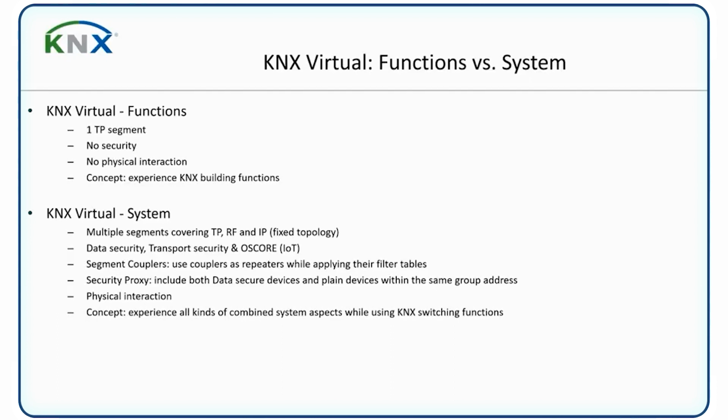So what is KNX Virtual System, to be more precise? In this virtual KNX installation, we will see multiple segments for different media types. So we will see twisted pair devices, radio frequency, IP devices, all that in a fixed topology, by the way. What we also have on board here is data security, covering also transport security, and also for the IoT part, the security is a technology called OSCORE, which I will also demonstrate here.